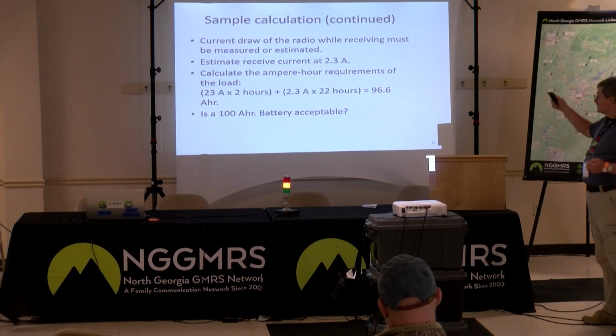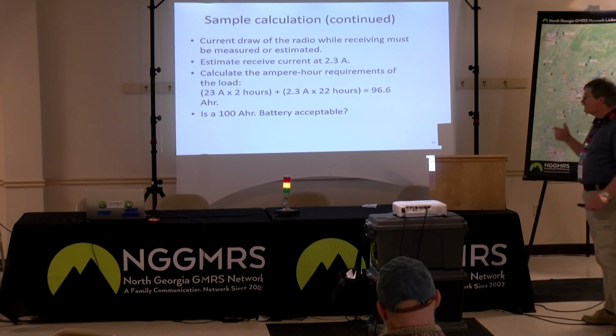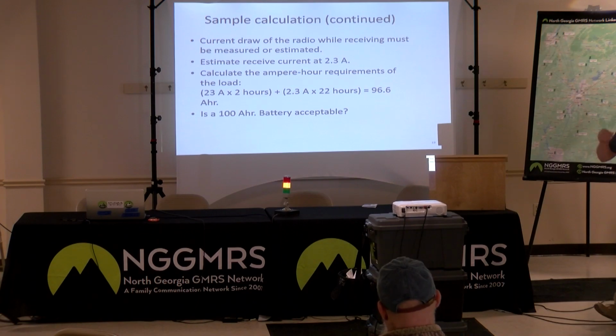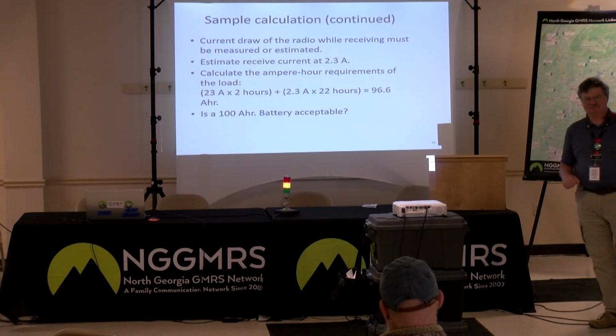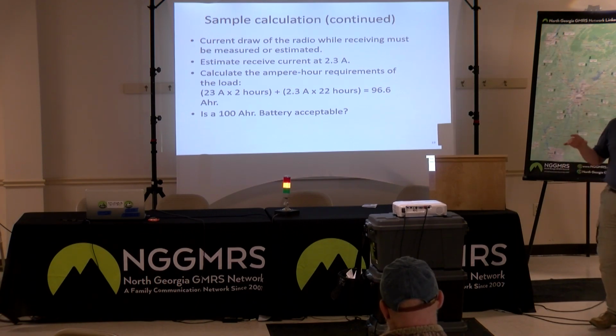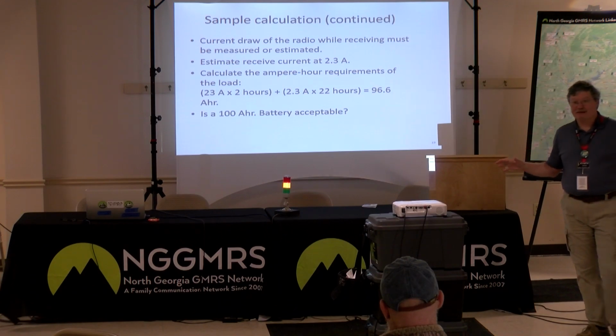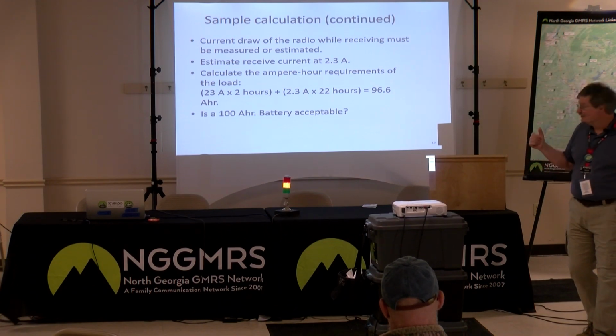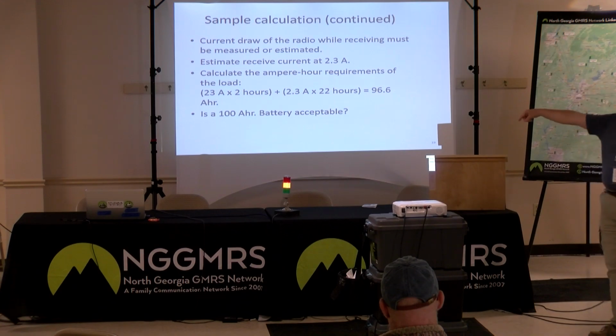So I estimated that. Now I calculate the ampere hour requirements of the load. But you said we're doing battery — yeah, but if I don't know what my load is, I don't know what I need for my battery. So for the ampere hour demand of my load: 2 hours at 23 amps plus 22 hours at 2.3 amps. Multiply it all, and that comes up to be 96.6 ampere hours.